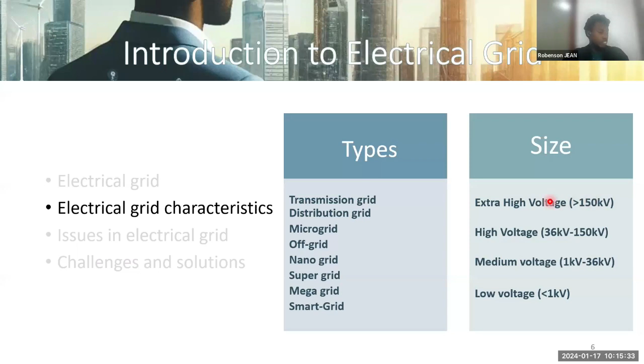And according to the size of the electrical grid, this helps us identify how we classify it, based on voltage. When dealing with less than 1000 volts or 1 kilovolt, it is low voltage. Medium voltage is between 1 kilovolt and 36 kilovolt. Above 36 kilovolt and under 150 kilovolt, it is high voltage. And above 150 kilovolt, we are dealing with extra high voltage.